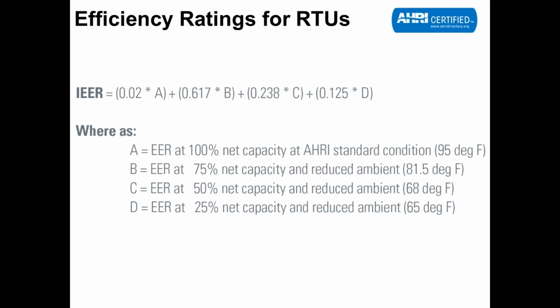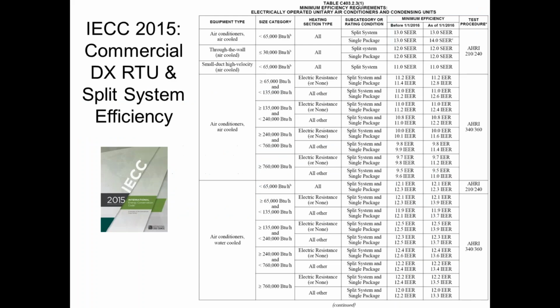And those efficiency ratings are what's used by the manufacturers and AHRI to rate the equipment, and they also fit into the code table, which is illustrated right here. So first thing to know is that if you have small equipment, small meaning under 65,000 BTUs, so less than 5 tons of cooling, you do not use EER or IEER. You use SEER, Seasonal Energy Efficiency Ratio, which is the residential testing metric. Even though you're doing this in a commercial building, in our case, you're still going to use that metric because that's how that equipment is tested.